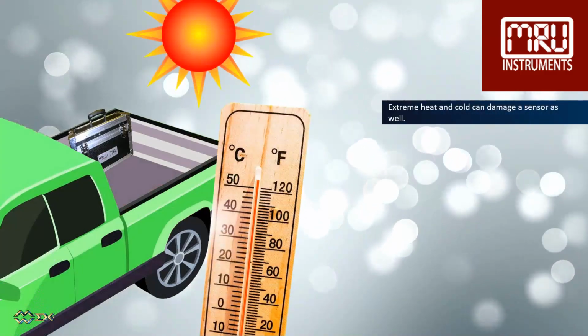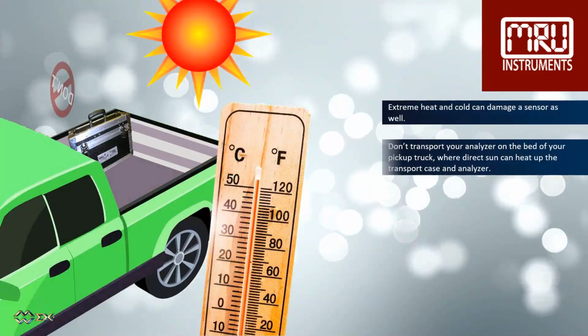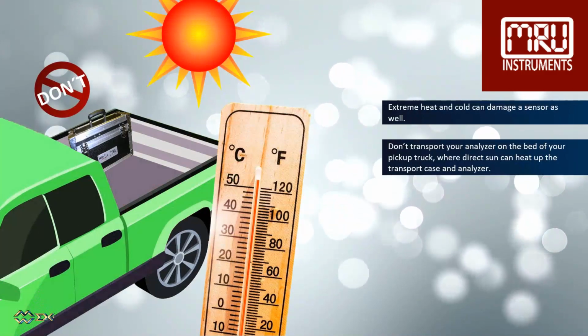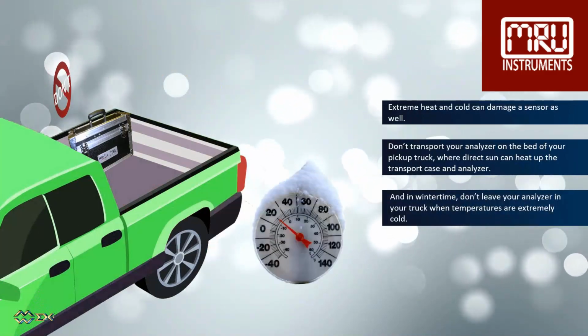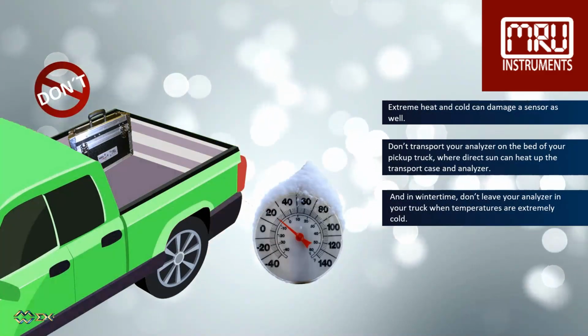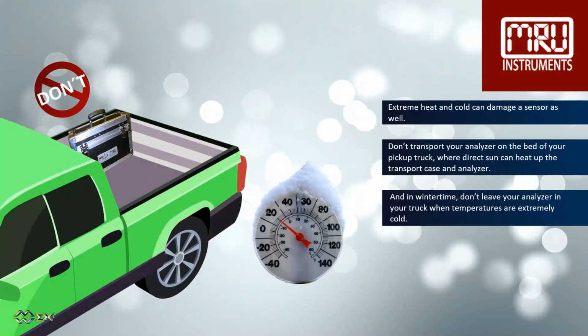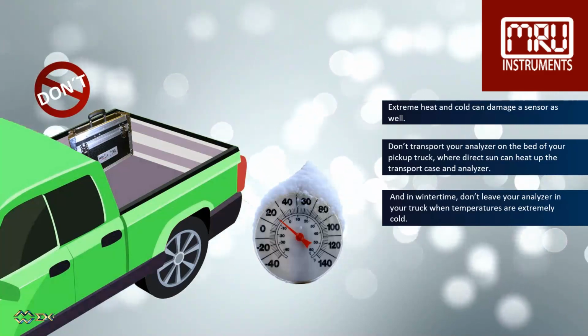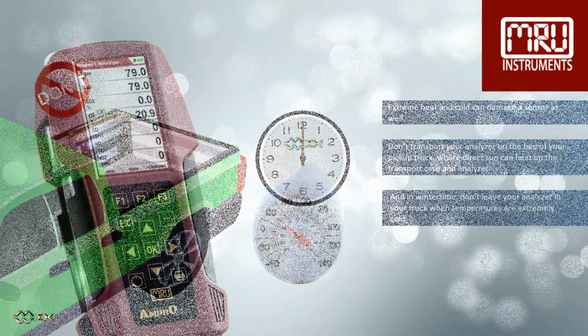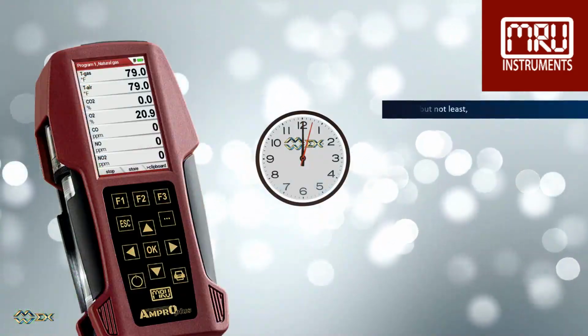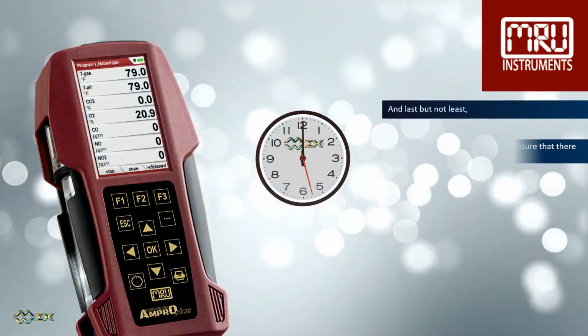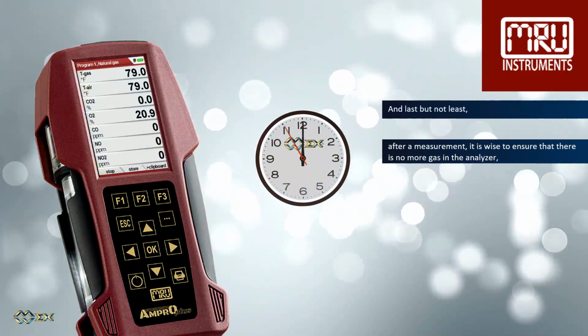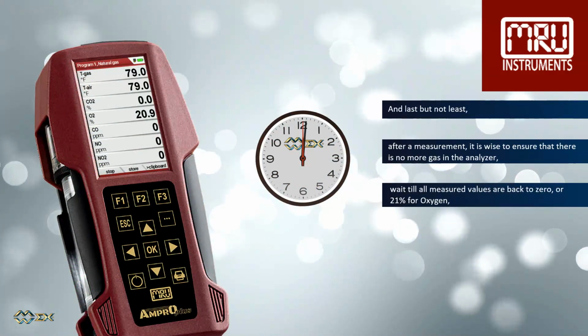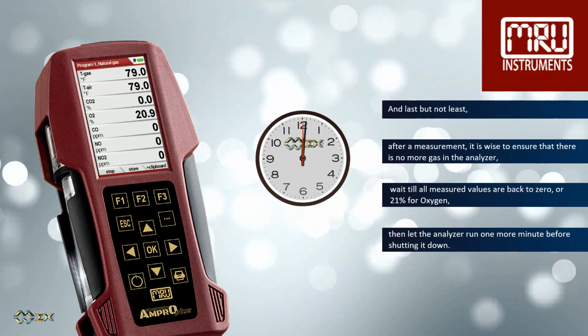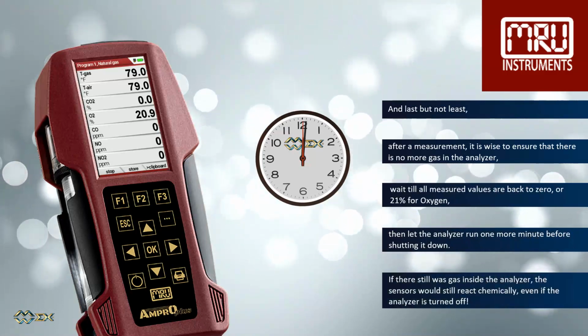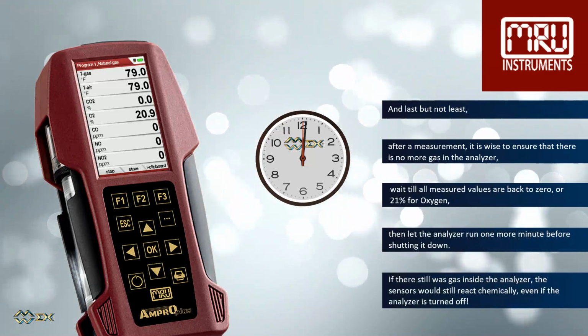Extreme heat and cold can damage a sensor as well. Don't transport your analyzer on the bed of your pickup truck, where direct sun can heat up the transport case and analyzer. And in wintertime, don't leave your analyzer in your truck when temperatures are extremely cold. And last but not least, after a measurement, it is wise to ensure that there is no more gas in the analyzer. Wait till all measured values are back to 0, or 21% for oxygen, then let the analyzer run 1 more minute before shutting it down.